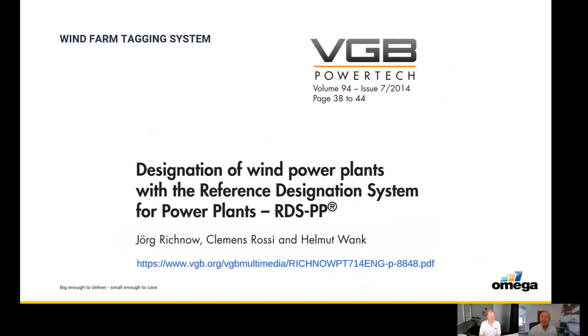The renewable energy sector has primarily adopted a tag structure known as RDSPP, which stands for the Reference Designation System for Power Plants — coming, as you can hear from the description, from the onshore power plant industry. For efficiency in planning, construction, and later in the operation and maintenance of the wind farm, it is necessary to structure the plant and assign clear codes to all components. These codes can serve as a unique reference address during engineering or as a functional location to allocate specific maintenance tasks in operation and maintenance systems, including the SCADA package.